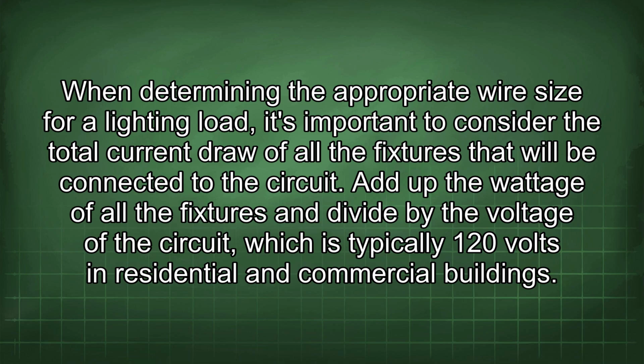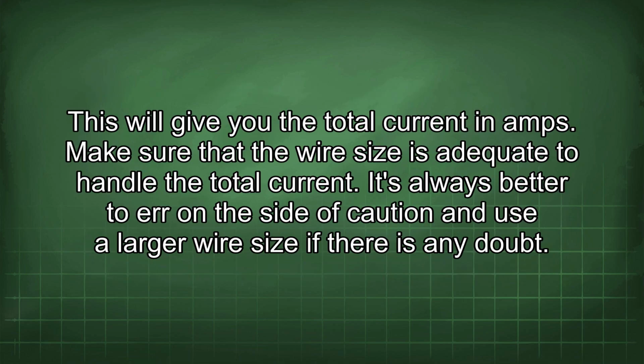Add up the wattage of all the fixtures and divide by the voltage of the circuit, which is typically 120 volts in residential and commercial buildings. This will give you the total current in amps. Make sure that the wire size is adequate to handle the total current. It's always better to err on the side of caution and use a larger wire size if there is any doubt.